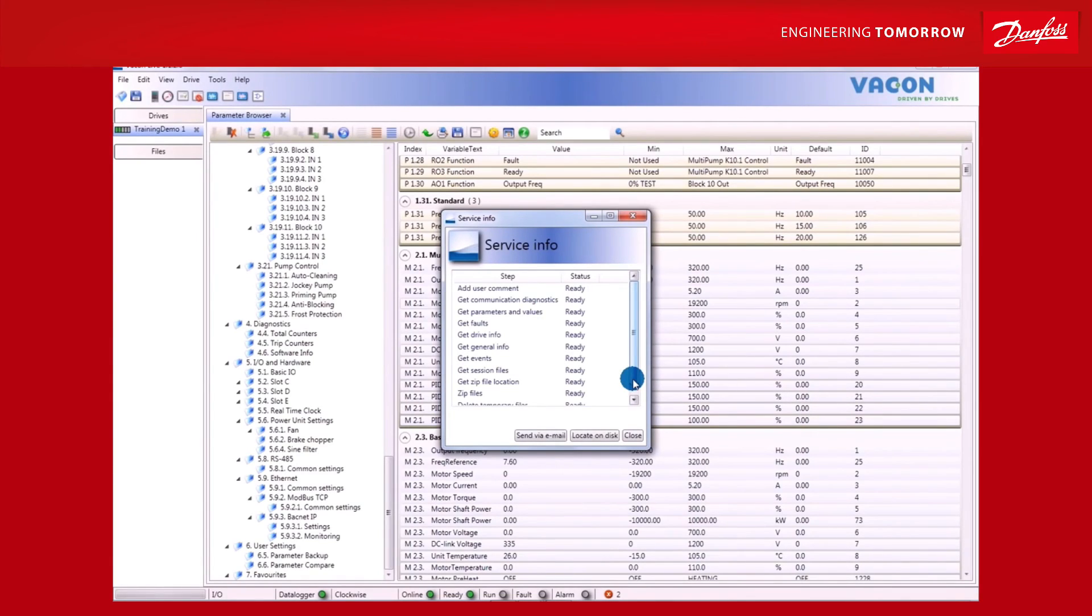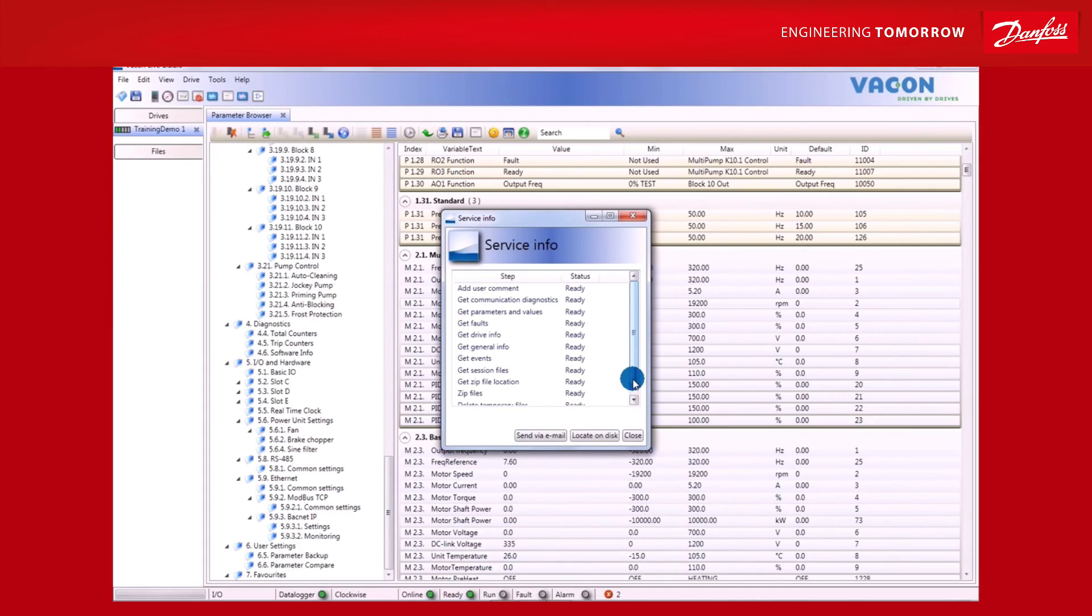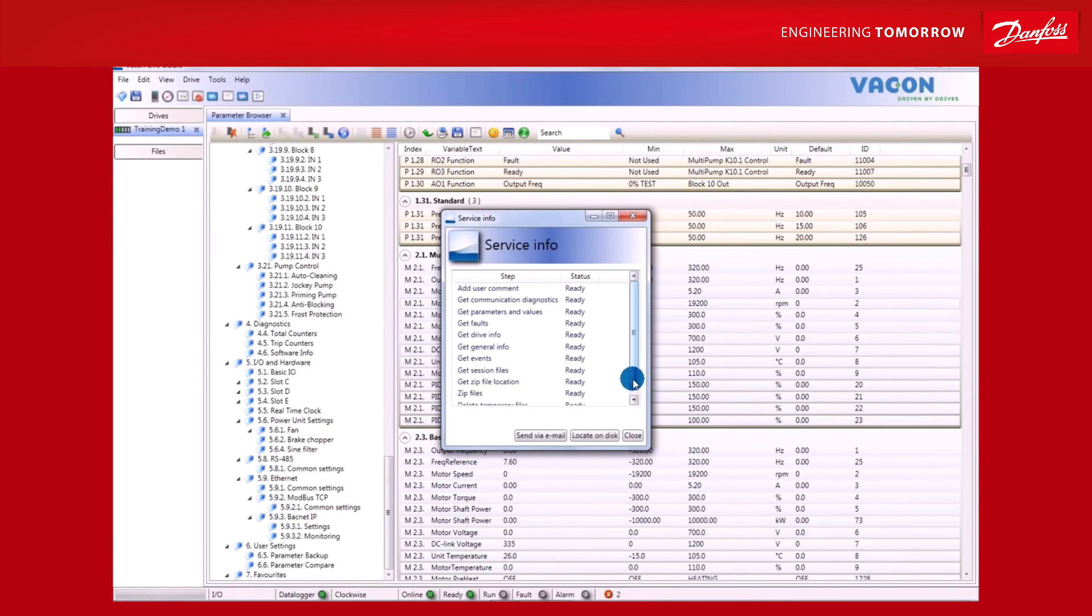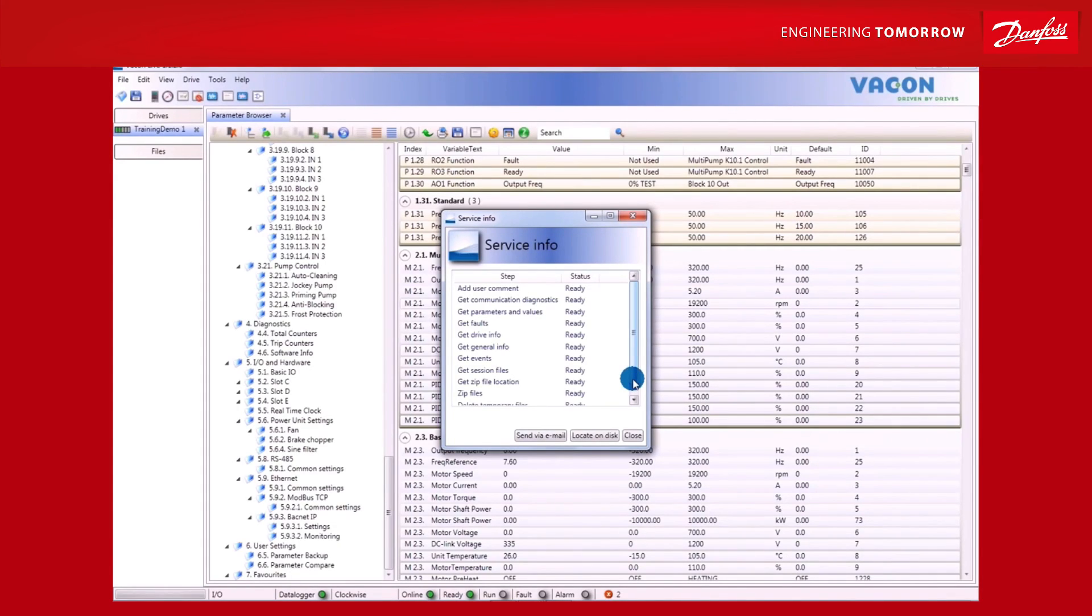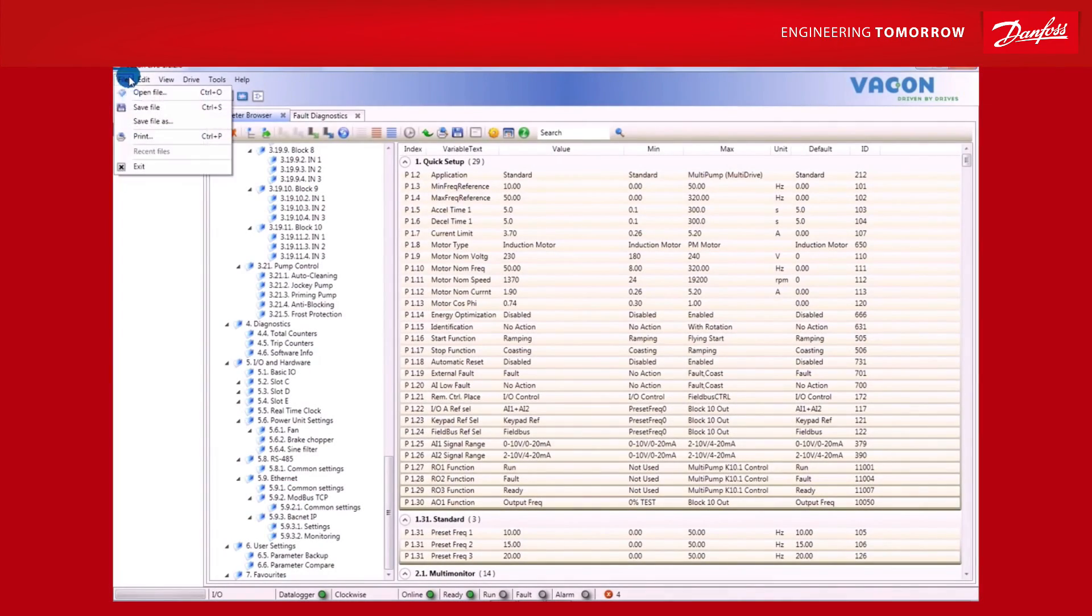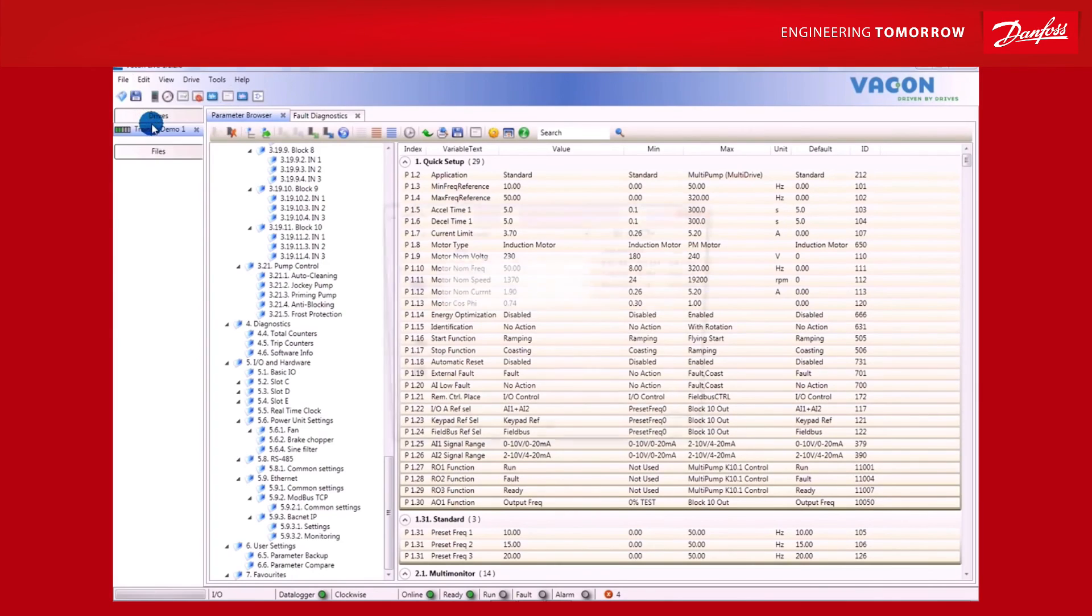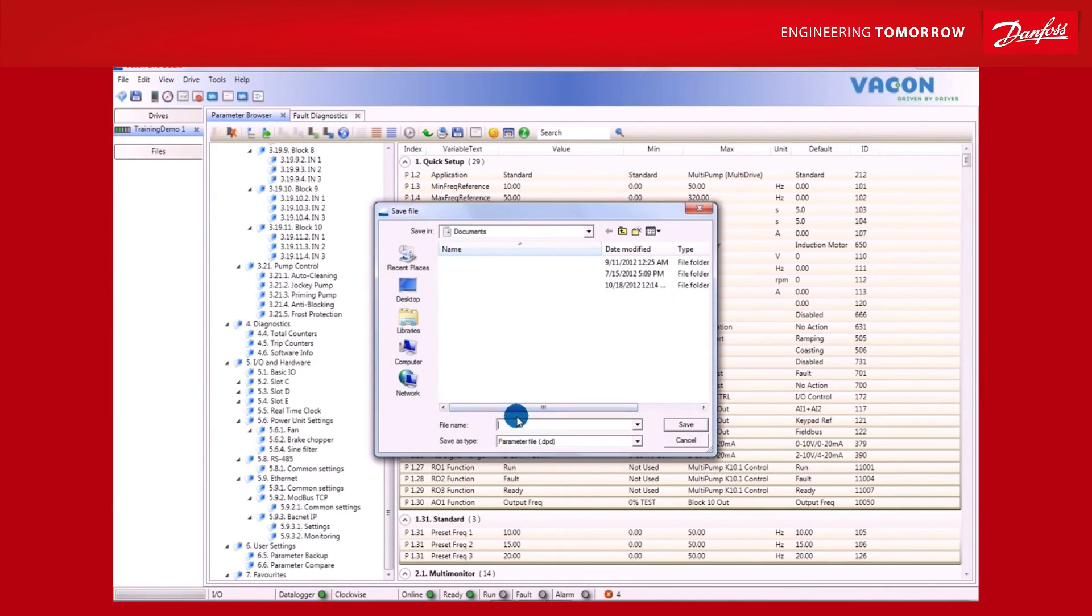The Service Report will be saved to your hard drive as a file, which you can then open in the location you desire. The Service Info page gathers and collates all necessary information from the drive and PC and gives fault logs, which you can send to a Vacon Service Center for further analysis when necessary. This saves time and money, since it means that all the data can be collected from the drive site and service site, so that a Vacon technician will only have to visit your site if strictly necessary. You can save almost all data compiled from VaconLive to your hard drive for later use, such as if you need it while offline.